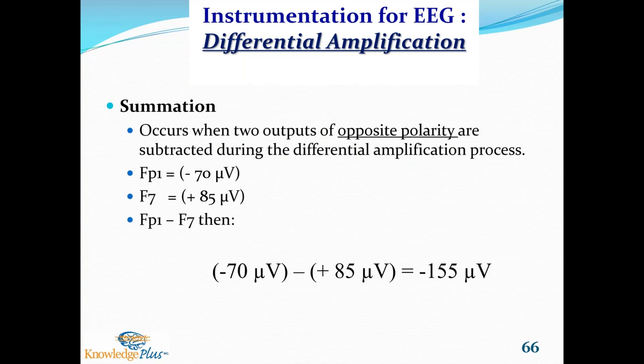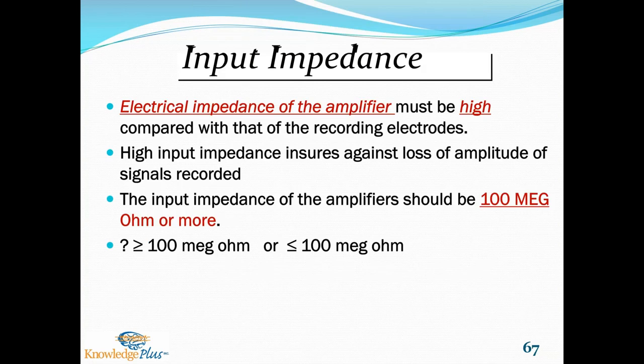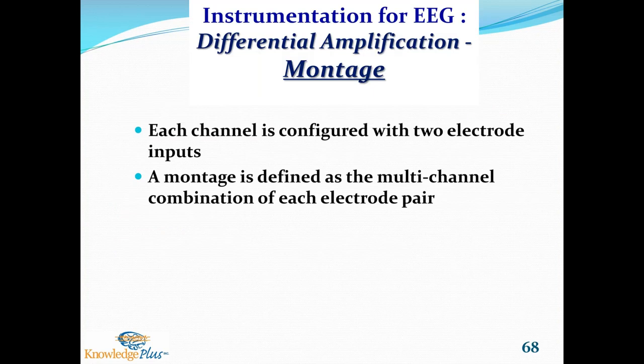Summation occurs when two outputs of opposite polarity are subtracted during the differential amplification process. As in this example, where input 1 is -70, input 2 is +85, and you get this huge output, very similar in numeric value but opposite sign, causing summation. In the guidelines, it says the electrical impedance of the amplifier should be 100 megohms or more. So when we talked earlier about any numeric value that you memorize for the exam, yes, memorize the number. Yes, memorize the unit, but also memorize the reference value, because you might have an equal to or greater than 100 megohm choice, or less than or equal to 100 megohm. So the answer is greater than or equal to 100 megohms. Of course, each channel has 2 electrode inputs into it.